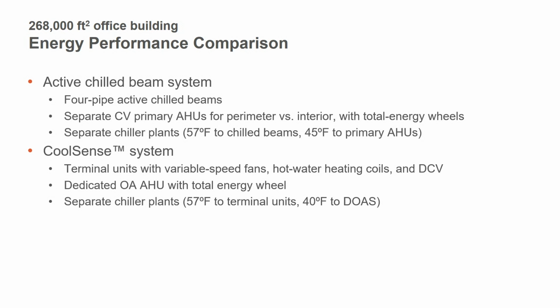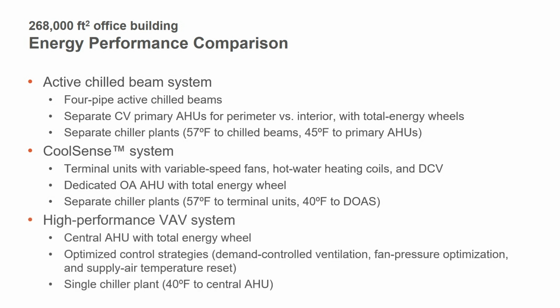Now, both the chill beam and CoolSense systems used separate chiller plants, one supplying 57-degree water to the terminal units and the other supplying colder water to the air handlers. Now finally, the high-performance VAV air handler had a total energy wheel and employed demand control ventilation, fan pressure optimization, and supply temperature reset. And this system was served by a single temperature chiller plant.